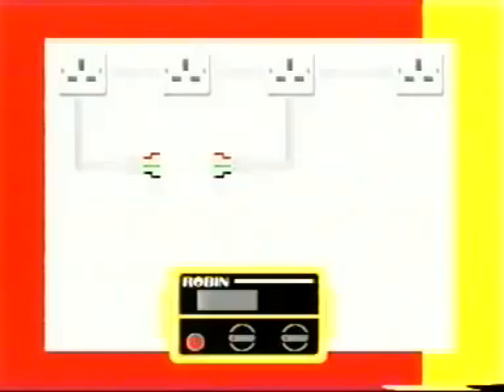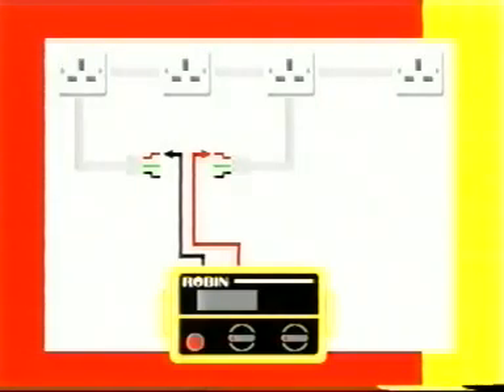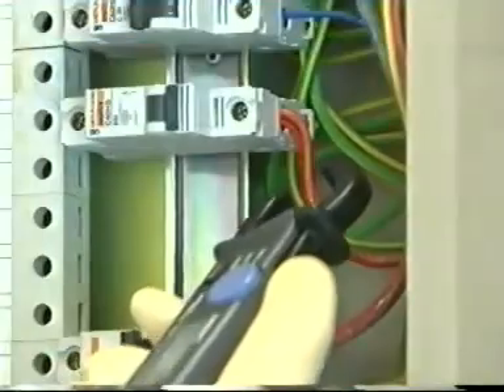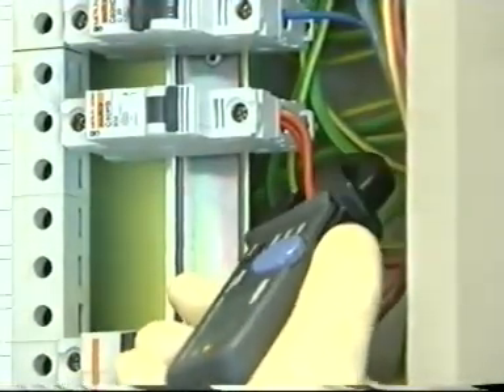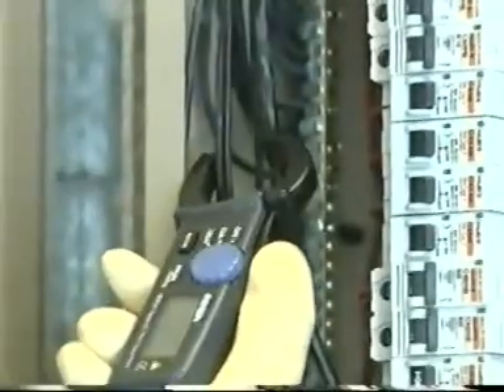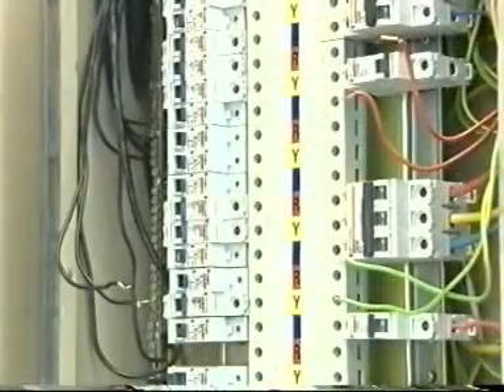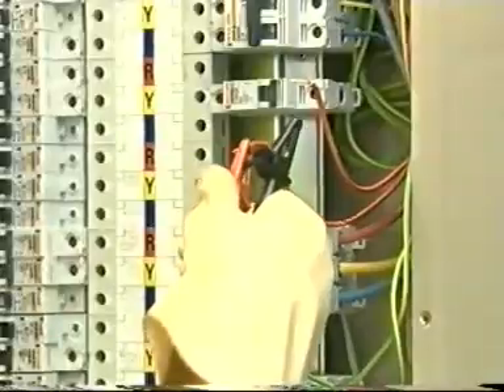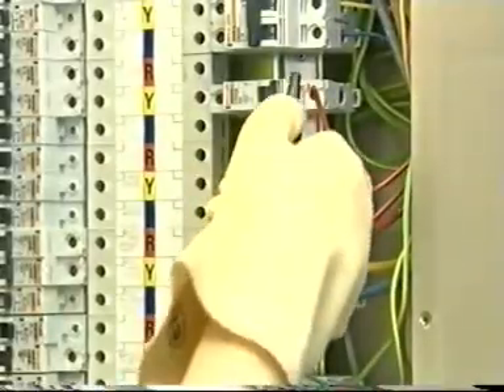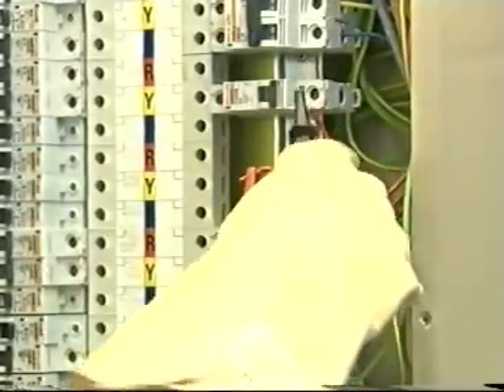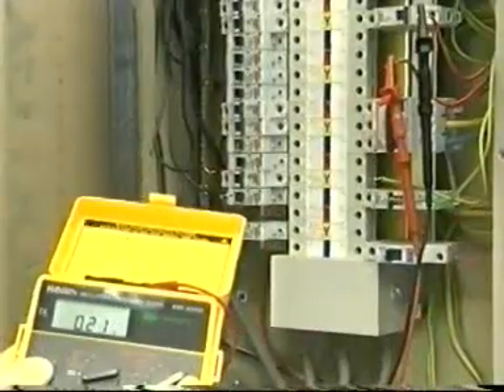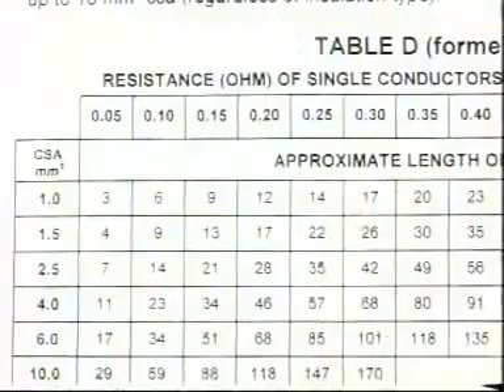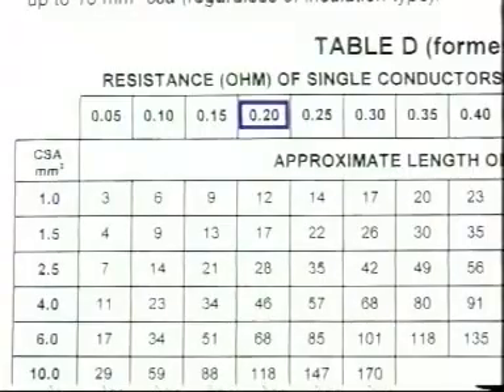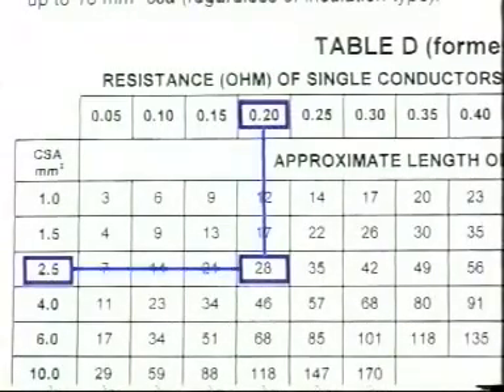It's important to ensure that a ring final circuit phase, neutral and protective conductor is soundly and correctly connected and continuous. After effectively isolating the supply to the ring final circuit and proving dead, the conductors are disconnected and their resistance measured and recorded. It can be seen from Table D of the Practical Guide to Testing that the conductor resistance can be directly related to conductor length.